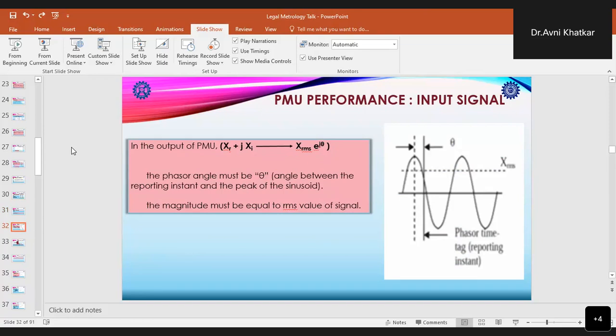From the performance point of view, when we talk about PMU performance, we have input signals to the PMU in the form of voltage, current and time inputs. For all these inputs, the output is the phasor estimate, with a time tag attached to it. There is also a phasor angle, known as theta, which is the angle between the reporting instant and the peak of the sinusoid. And the magnitude is equal to the RMS value of the signal.